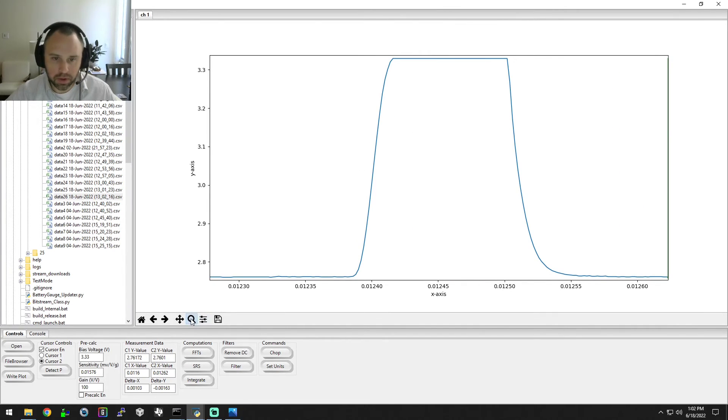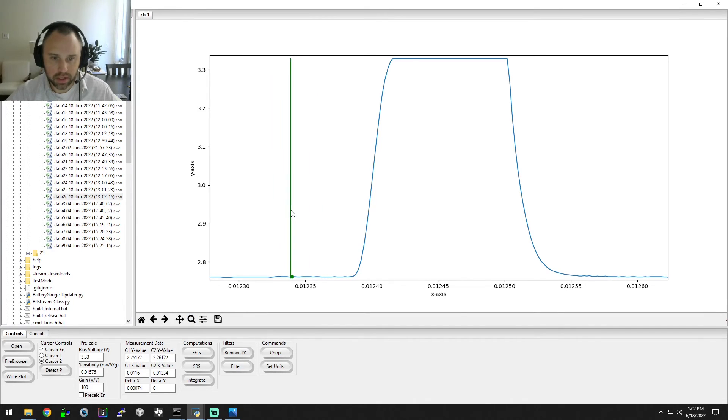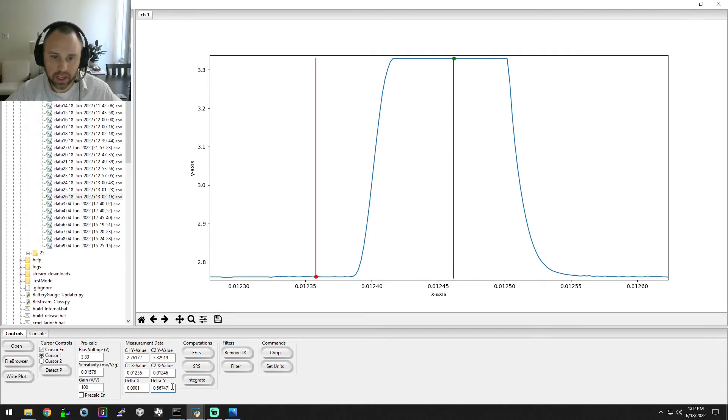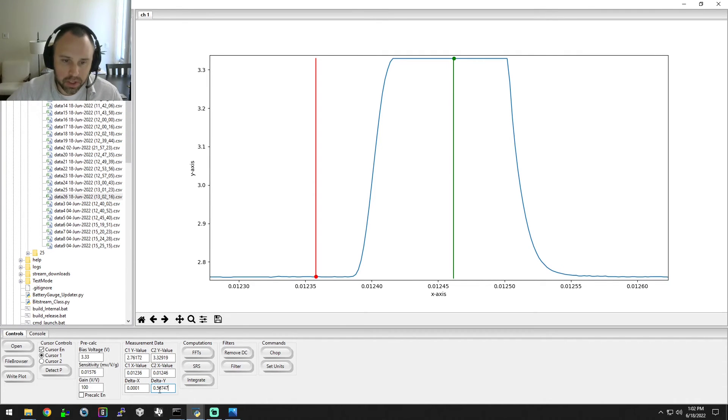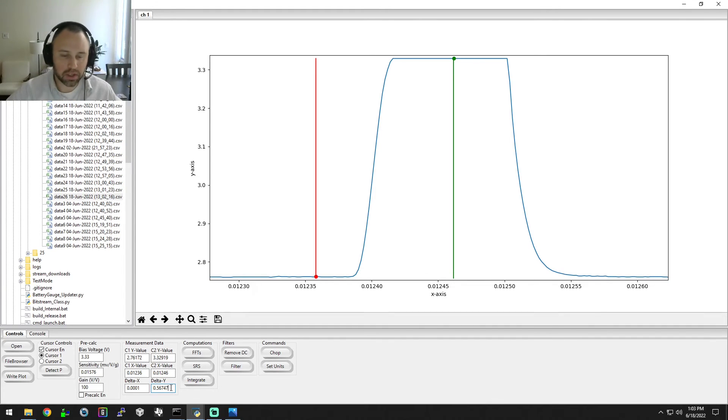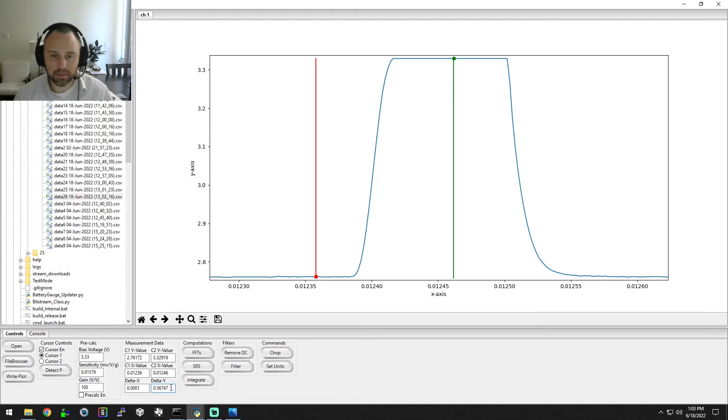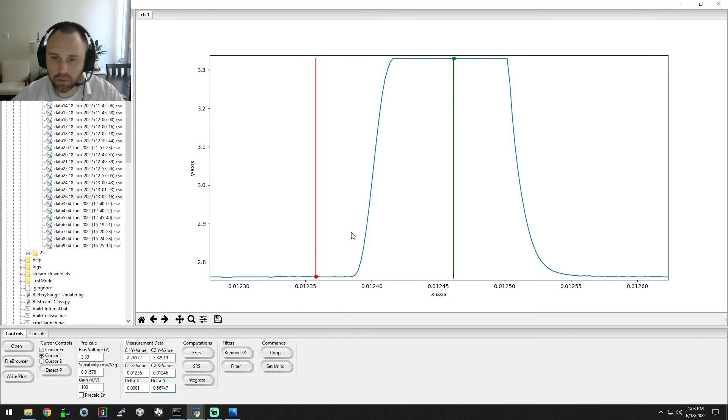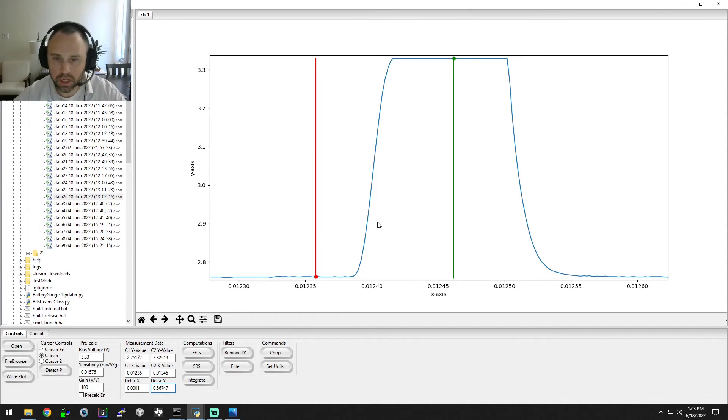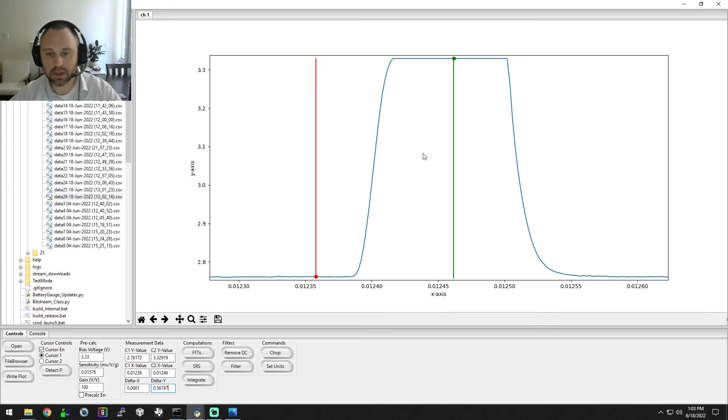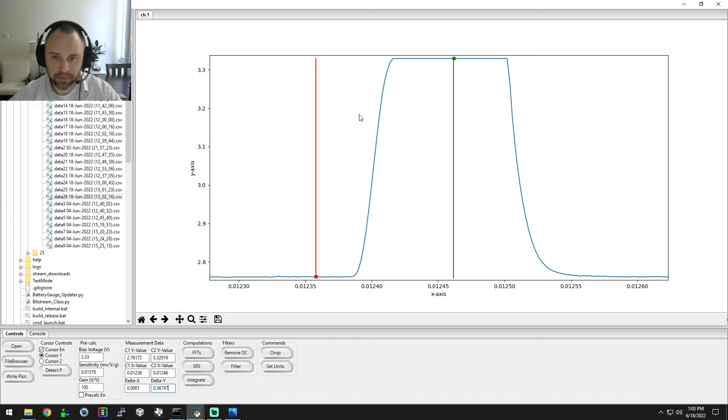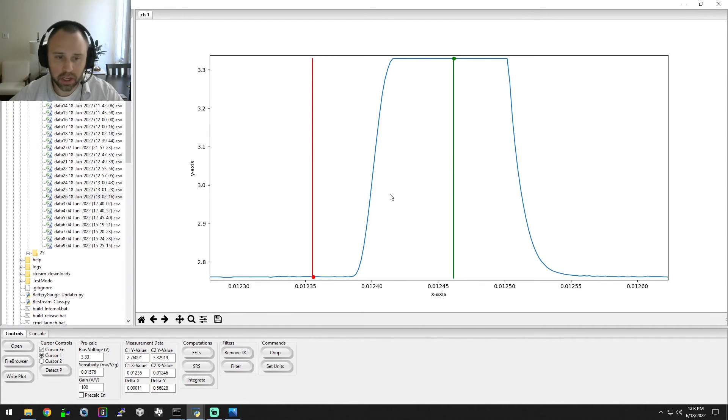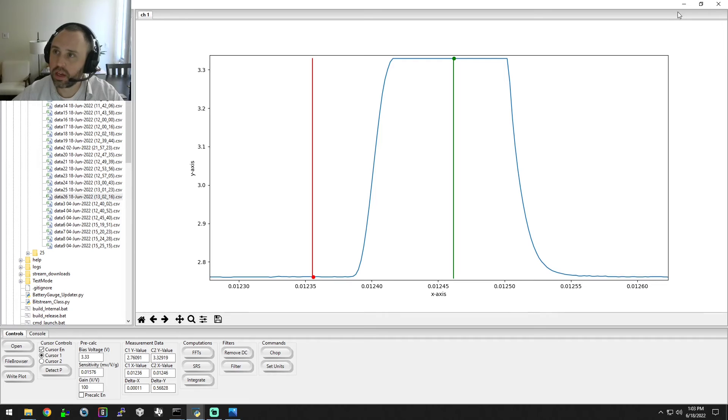This is pretty common, especially when working with either more exotic asymmetric sensors or custom third-party electronic systems that you're trying to synchronize to a sensor. For example, shock electronics on channel 1, or shock accelerometer on channel 1, and then channel 2, 3, and 4 may be connected to customer hardware that's under development. In this case you would be losing about 300 millivolts of information, so this would render the data acquisition run useless. So to fix this all the user has to do is launch the offset DC offset calibration HUD.